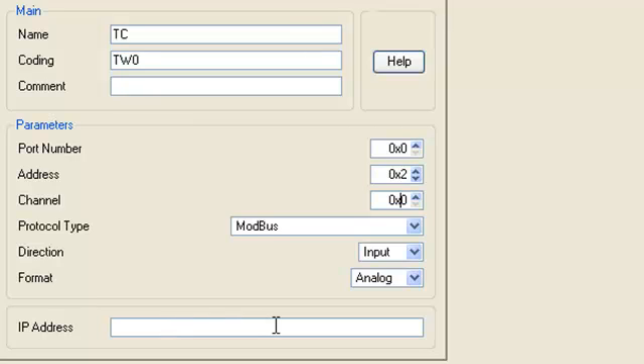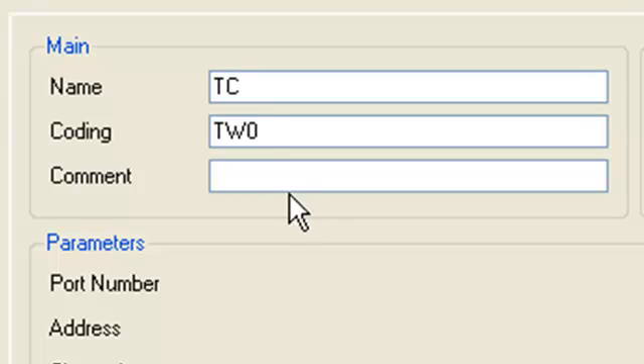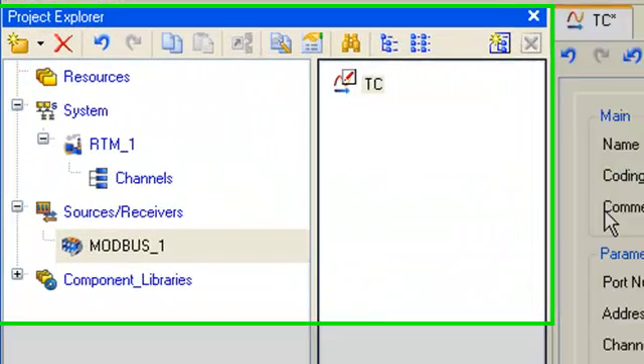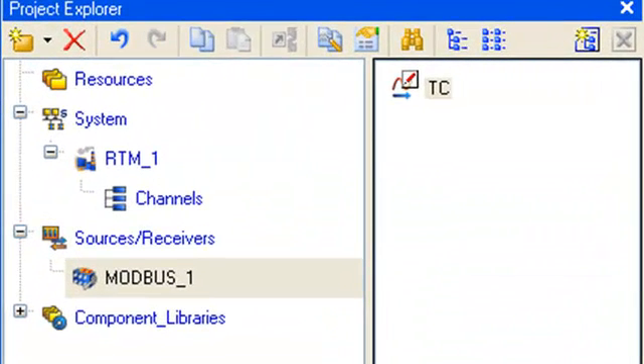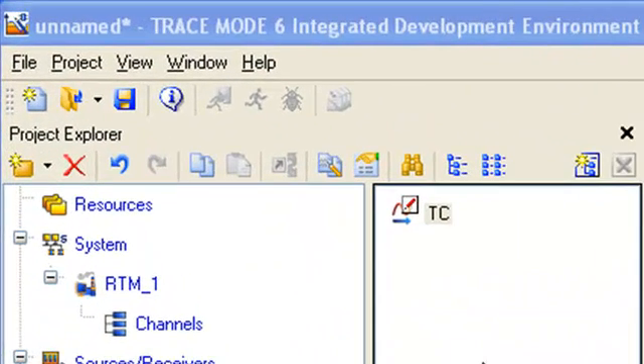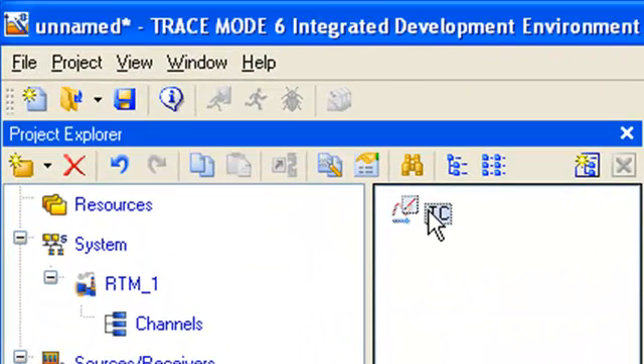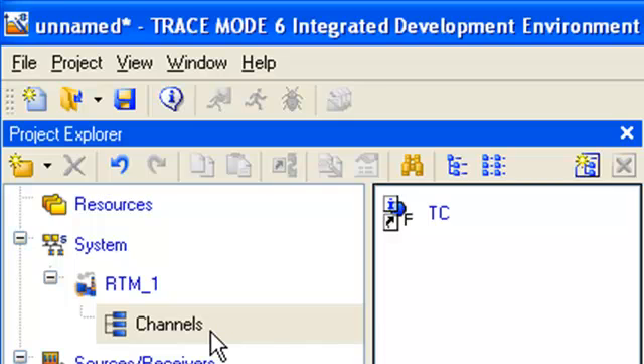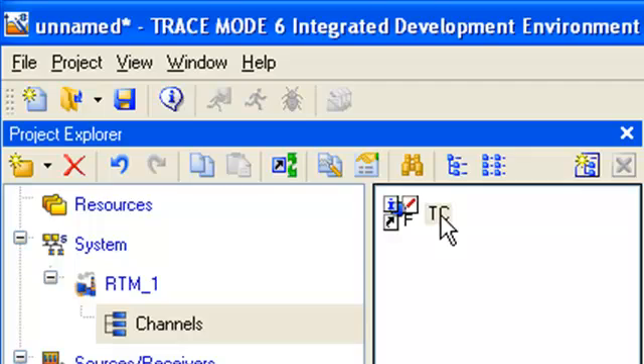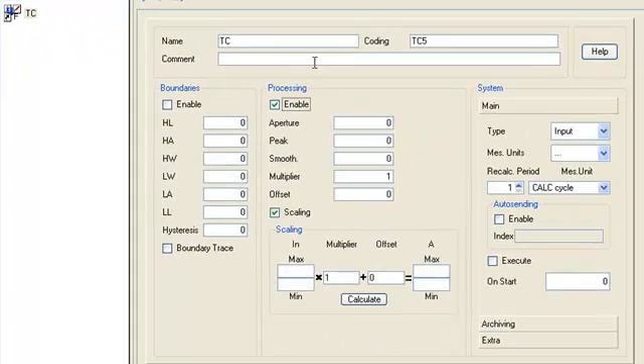The setting IP address is blank. In order to the data about temperature was requested from the remote device via GSM, in the field comment, we type its phone number in the international format of a SIM card inserted to the remote modem. After that, we drag and drop this component to the group channels of RTM1 node in a project tree. Let's open the created trace mode channel with the name TC for editing and let's set flag enable in section processing.